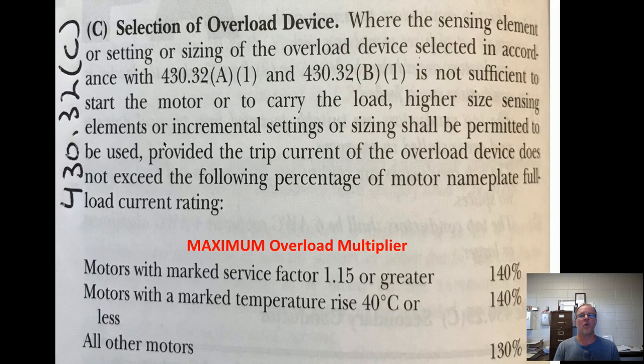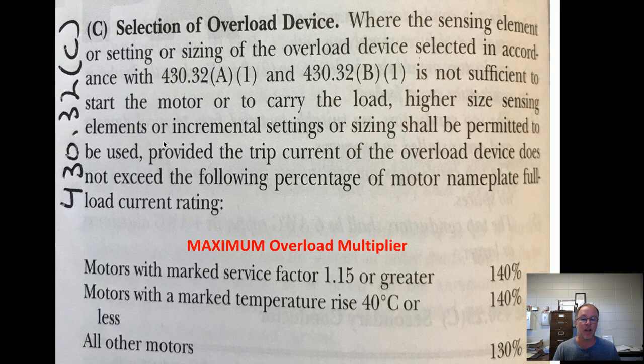What if the question says maximum? The only time you use the maximum chart is when the question says the word 'maximum.' If it just says 'what is the overload protection,' you use minimum. But if it says maximum, you use these multipliers. It's the same logic as minimum regarding service factor and temperature rise: service factor 1.15 or greater goes to 140%; temperature rise 40 degrees or less is also 140%; all other motors are 130%.